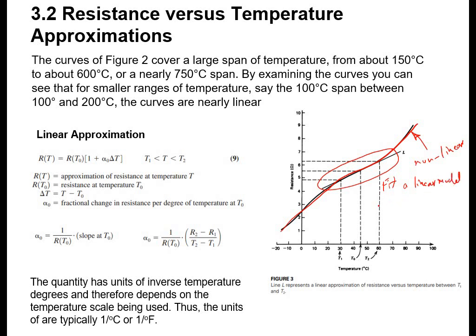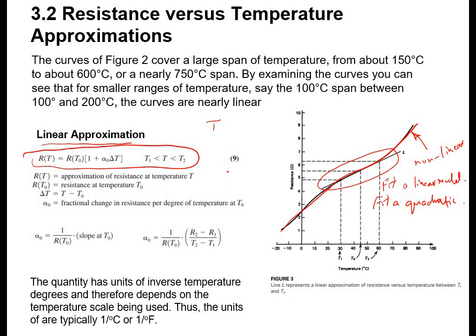However, a linear model will not be very accurate, or we can fit a quadratic model which will be more accurate. So we are going to have two equations — one for the linear and one for the quadratic. It depends on what I need to achieve. Talking about the linear approximation, the equation is R = RT0 · (1 + α0 · ΔT). R and T represent data points: T1, T2, T3, and R1, R2, R3, and so on.